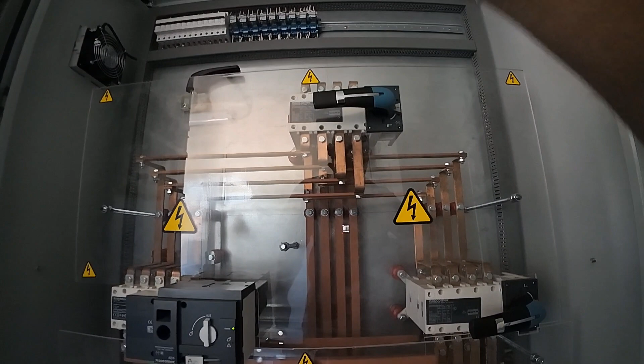So fully automatic. Now we're going to activate our load side. This is our bypass for the load side, so we can bypass directly for our mains and for our generator. So this is the load - one is for our load from this ATS, so we can put it in number 1 to have the load supply. As you can see, the fan is working now. So we will take a look over here.